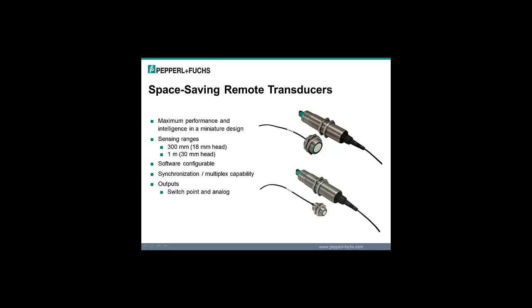If a customer does need maximum range in a smaller space, it's a general rule that ultrasonics don't really have the space restrictions that an inductive needs, but it can certainly happen. So if you need high functionality and high power, we have remote transducers where the transducer element is all that's in the circular housing. And then maybe 1 meter away, you have the driver electronics mounted. So you can put that tiny little sensing head in a lot of space restrictive applications and then have the driver electronics located a yard away or 3 feet away. So it gives you some options that you couldn't get otherwise in the smaller barrel like the half pint size.